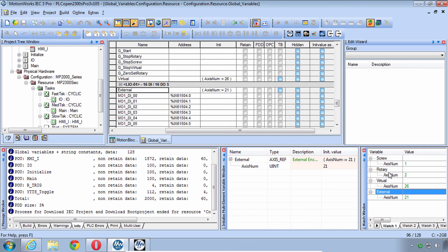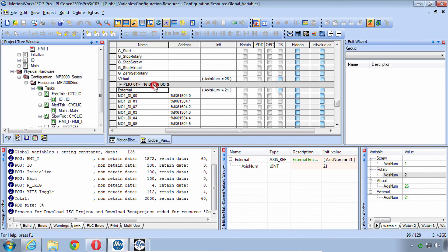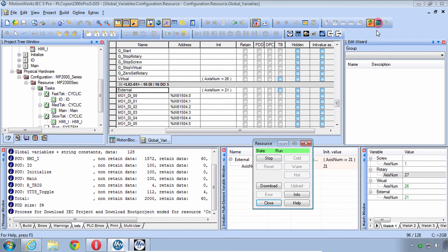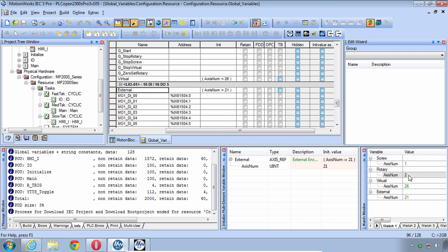Again, if you're doing the MP2600 IEC, then the Rotary you should have set to 27. And of course, you could overwrite these; this wouldn't usually happen. You can overwrite these, and you'll notice then, if you do a Stop and a Warm Start, they'll go back. Stop and a Cold Start, same thing. These variables are not retained. So that's why whether it is Warm Start or Cold Start, the initial value is applied. And I think I would leave it that way. We really don't want these to change; otherwise, you'd start controlling a different axis if it existed. Very well. We have each of the axes now initialized to the correct logical axis number, and we can proceed with our program.